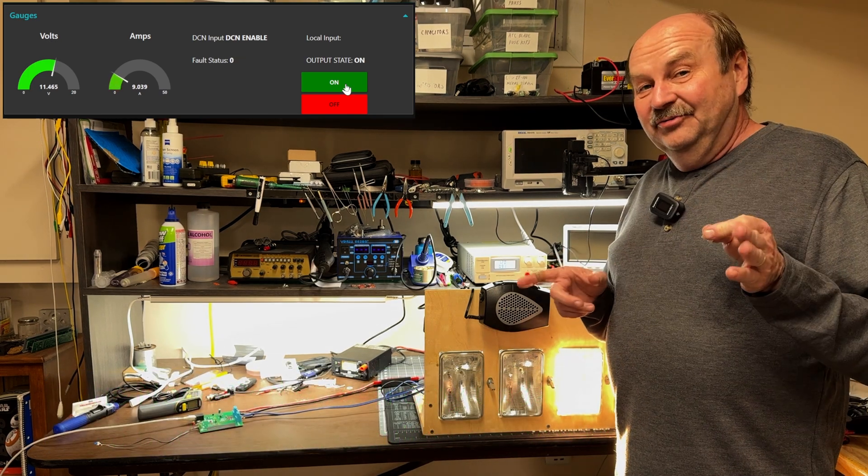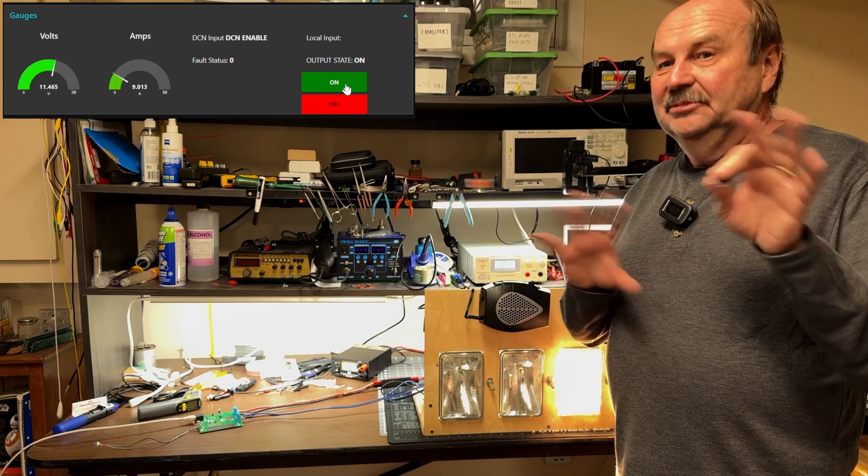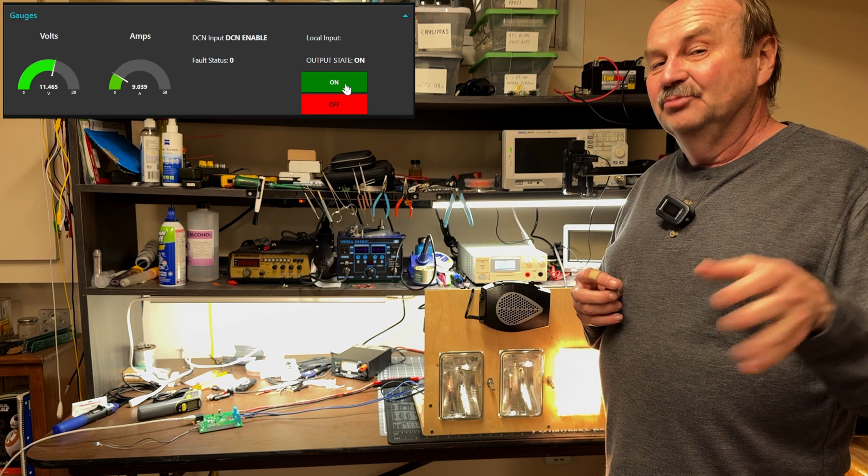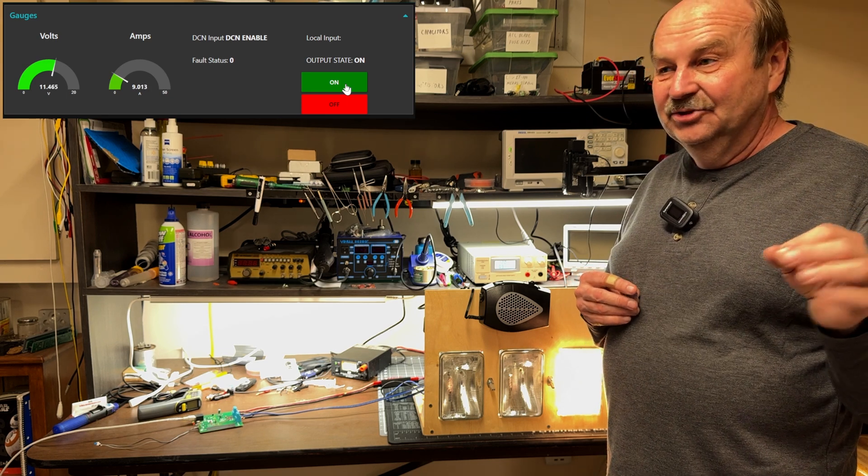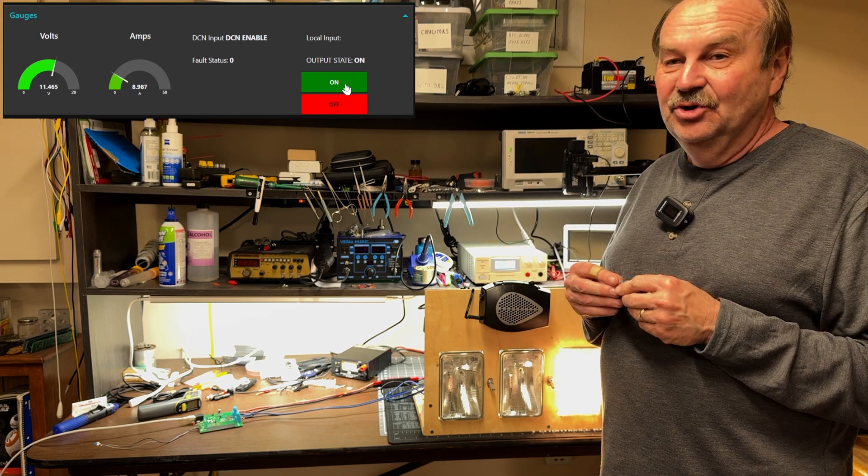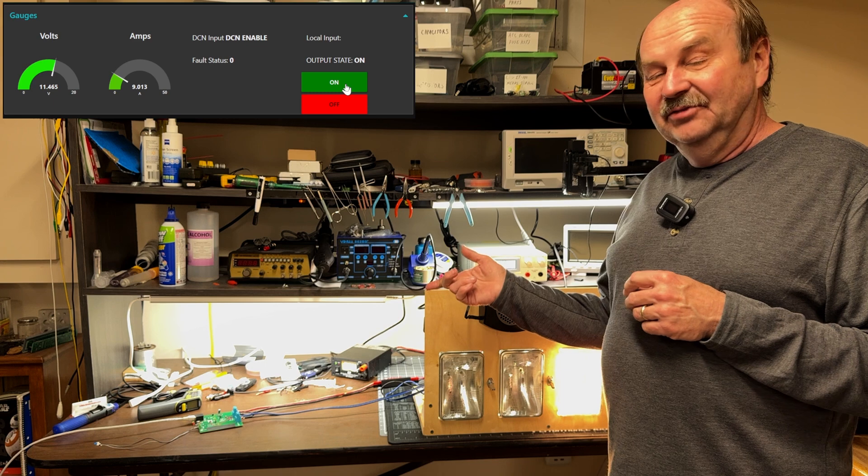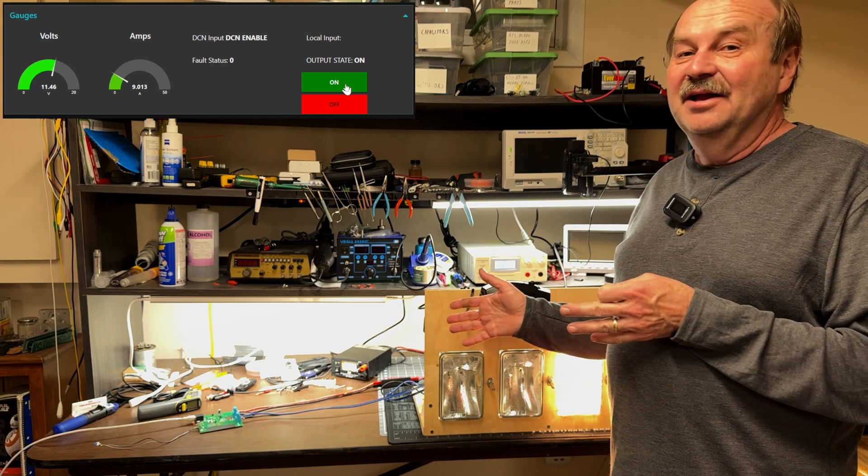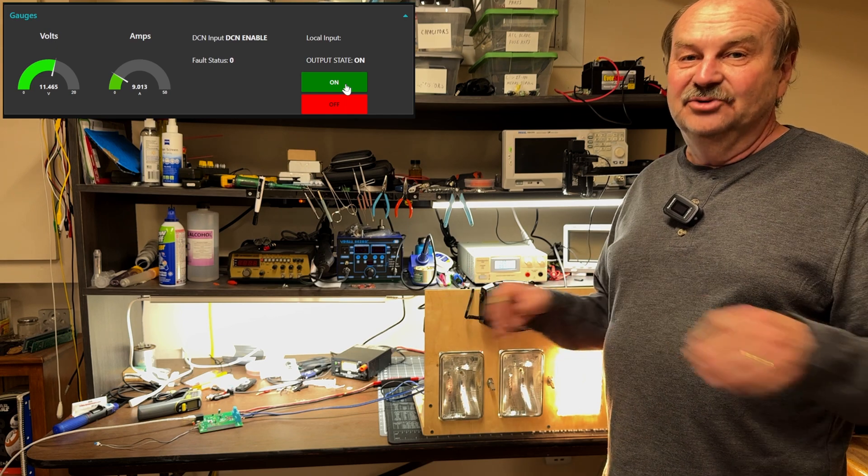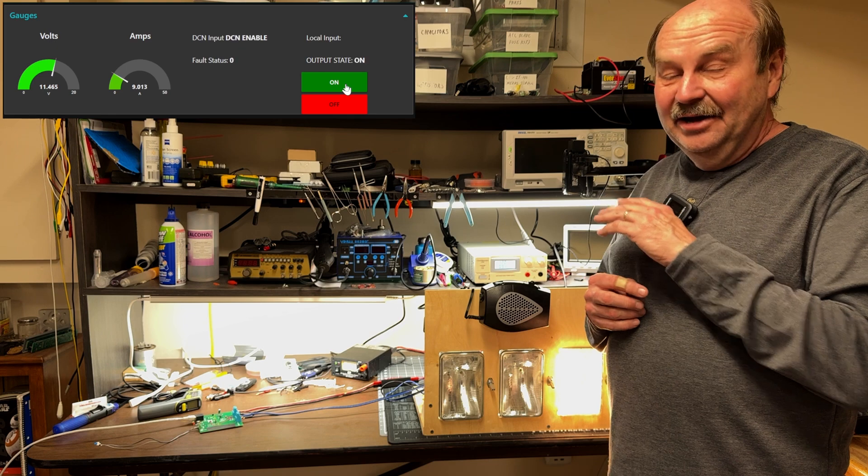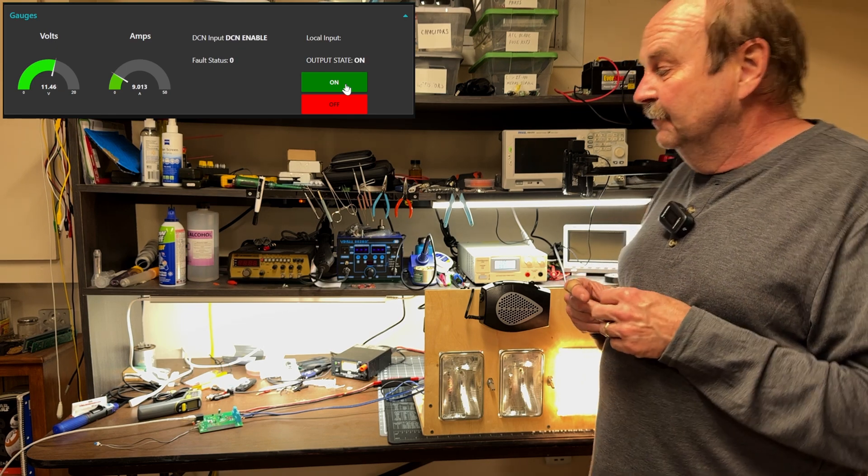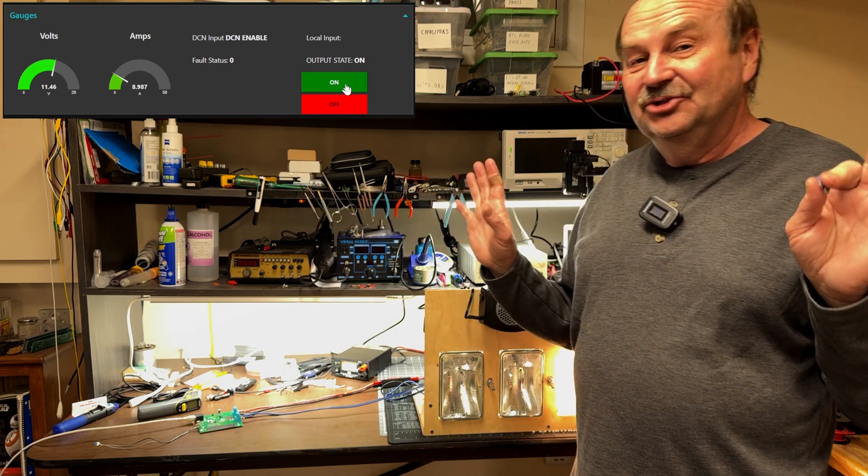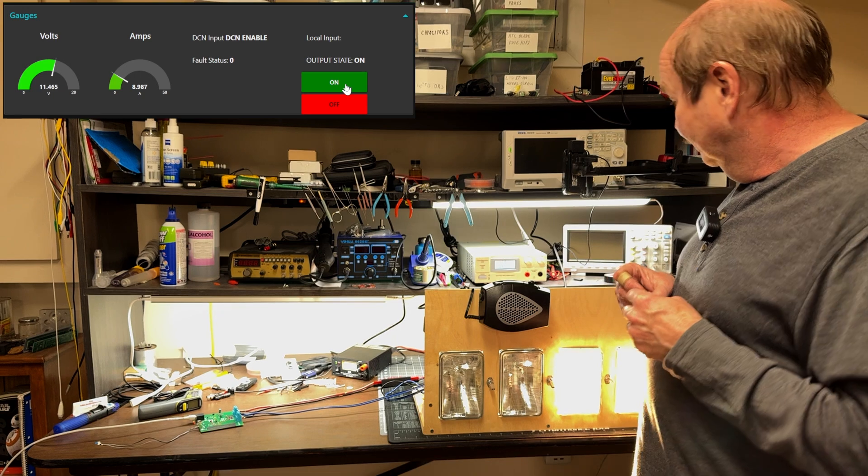Now, one of the features that this will have, it's not in the firmware yet, but it'll be in the next phase. Before it's in production, this will be in there. Another feature is there's a maximum retry count. So, if you have something that's like really a hard short, where something has actually gone bad, you could have it set up to retry, say, 3 times, and if it doesn't stay on after 3 retries, then it stays off. You can also set the overcurrent so that, on any overcurrent, it goes off and stays off until you turn it off and back on. Don't need to change any components, you just have to turn it off and back on, and then that'll reset it.